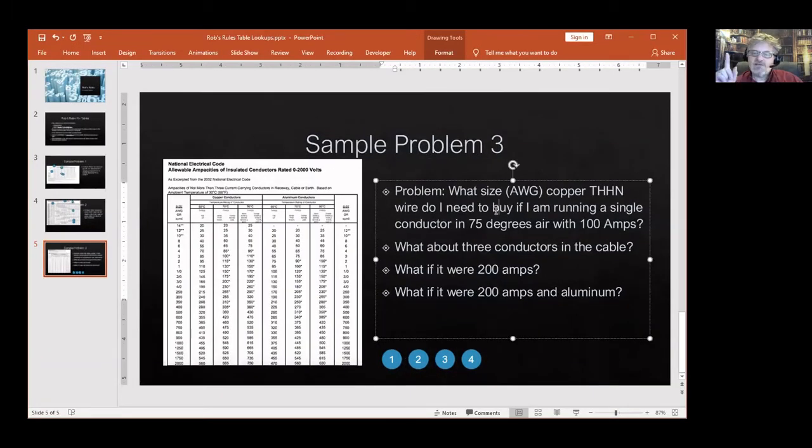The problem is what size, in this case we're using AWG as the American wire gauge, the standard size, copper THHN wire do I need to buy if I'm running a single conductor in 75 degree air, which is your generic standard for a reasonably temperature controlled environment like an indoor environment, with 100 amps of power. 100 amps is a lot of power. A normal whole house is set up with 200 amp service so 100 amps is half of what a house would normally take.